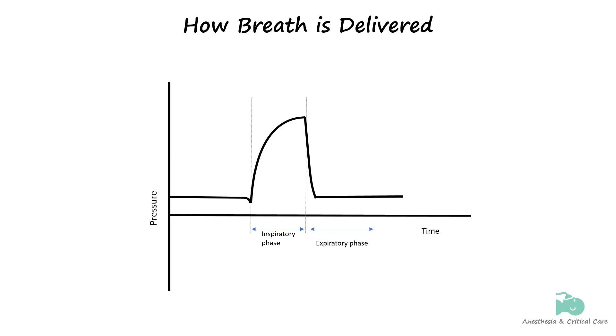Before reviewing the graphics associated with mechanical ventilation, it's important to understand how ventilators deliver breaths. A mechanical breath is classified based on three main variables called phase variables. They dictate how the breath starts, how it's delivered by the machine, and how it stops. A breath can be started either by the patient, called a supported or assisted breath, or by the machine, called a controlled breath. This is known as the trigger.